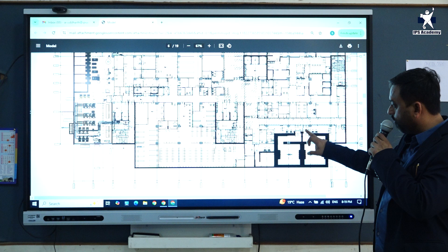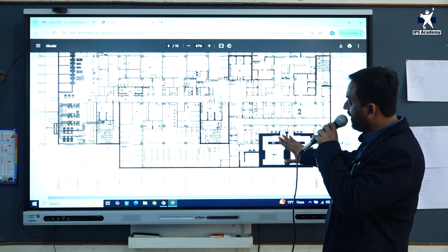These are the black highlighted walls - you can see the thickness - these walls are for the LINAC, linear accelerator. Similarly, other radioactive zones next to the corridor, like PET-CT and SPECT-CT, have an area of about 800 to 900 square feet, with 9-inch thick walls so that radiation is controlled within these areas. In basement 2 as well, we have to plan the utilities in terms of services.